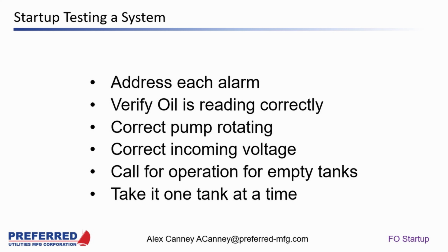Right, and that brings me to something we're seeing a lot of here in the Boston area. I don't know if this is somewhat unique to generator systems, but a lot of times before we're even allowed to put fuel into the tank, whether it's the main tank or the day tanks, we now have to have, at minimum, leak detection fully tested and maybe observed by the local authority. Do you see a lot of that?